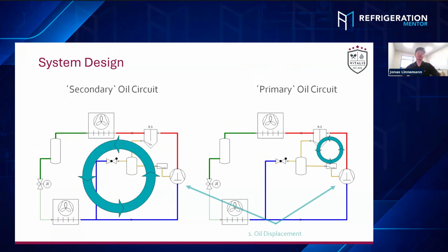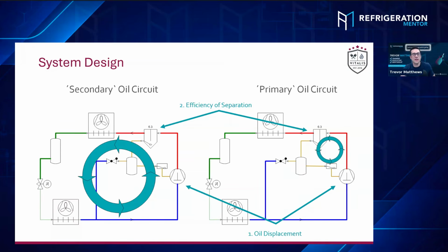And there are basically two different factors which are important for the differentiation between primary and secondary oil circuit. The one is the oil displacement, because the higher the oil displacement of the compressor, the more you also get out into the secondary circuit. And the second most important factor is the efficiency of the oil separator, because whatever amount you can separate from that discharge line, that's the good oil. Yeah, because nothing is 100% efficient. But we need to make sure the pressure drop across it is correct, that it's not plugged, and that the viscosity of that oil doesn't get too hot, or even too cold, you know what I mean?